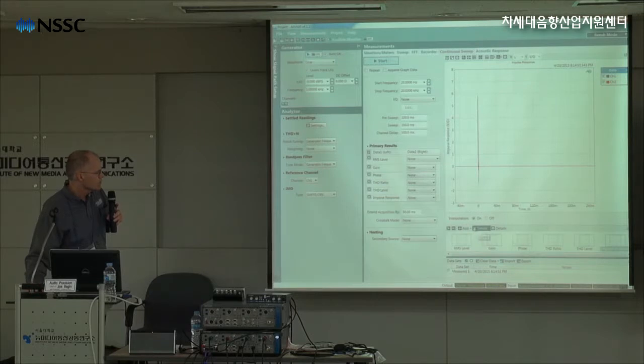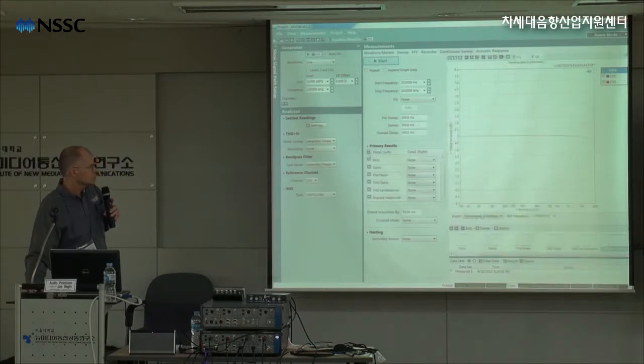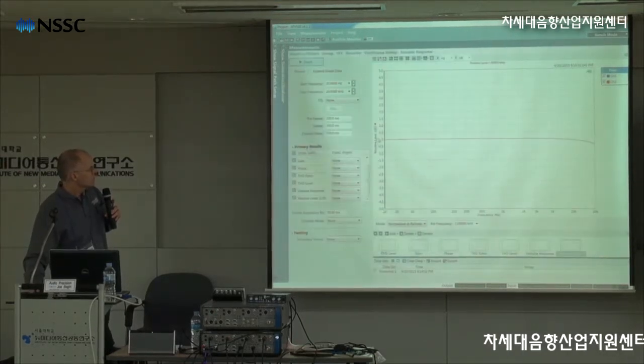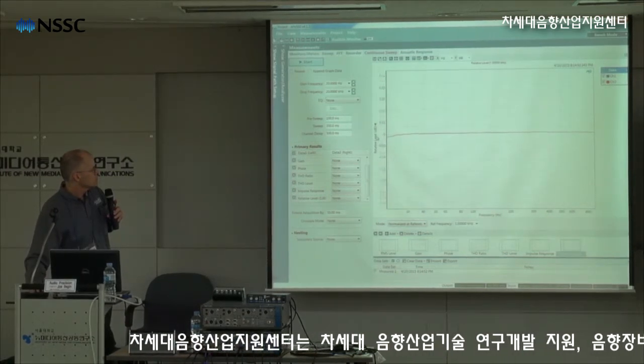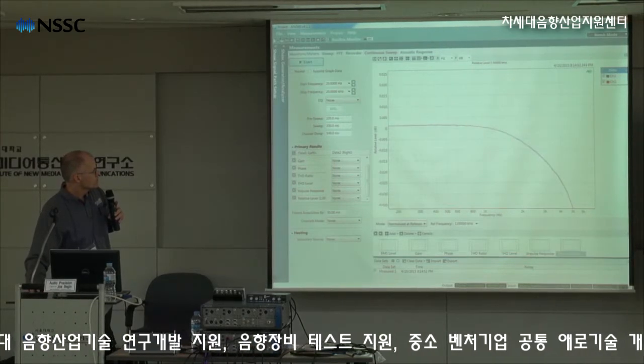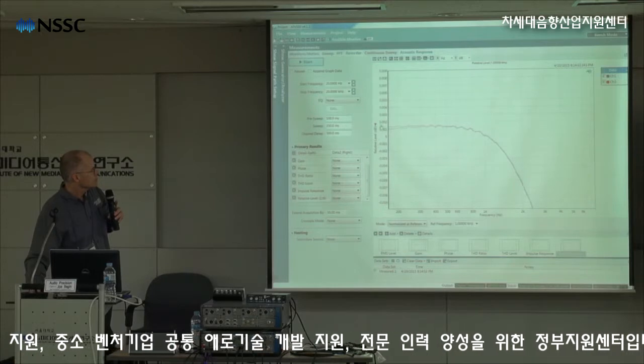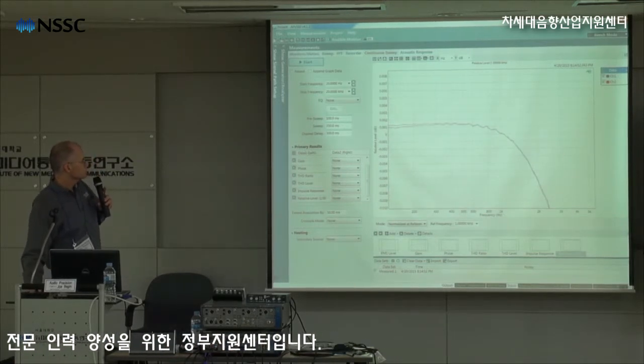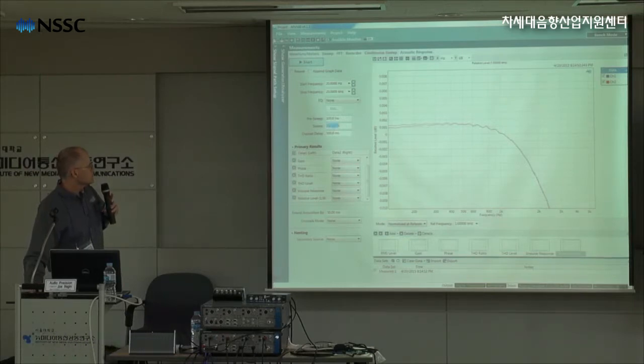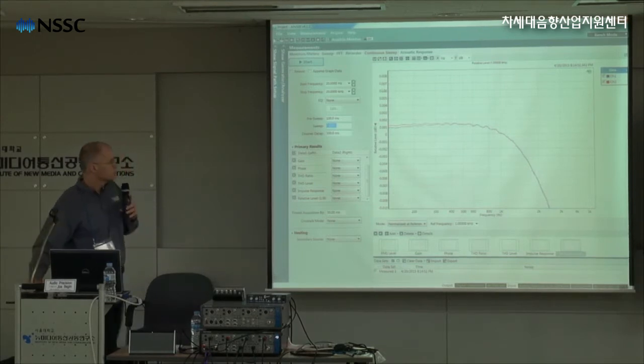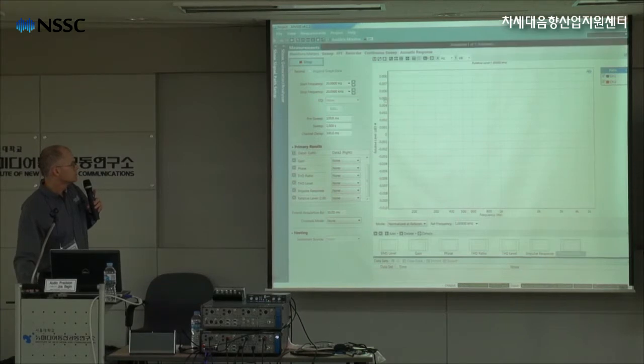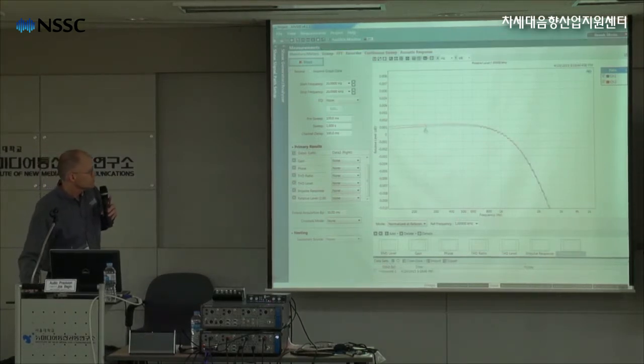So if we add a primary result called relative level, this shows the level relative to, it's normalized at a frequency of 1 kilohertz. And if we zoom in here a little bit, you can see the response. You can see some ripple in the passband here that's occurring at certain frequencies. If we wanted to increase the resolution, we could use a longer sweep here. Default is 350 milliseconds. Let's try a 1-second sweep. So you can see the ripple.